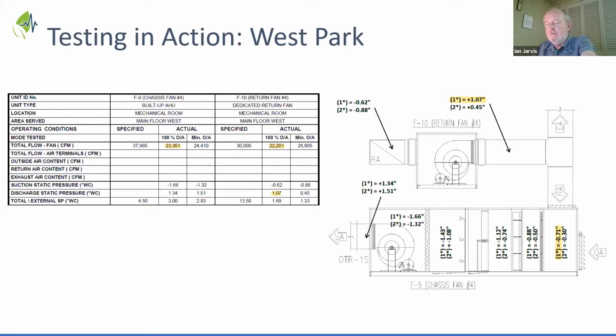But when we have the return fan at 100% outside air delivering at the top, there you'll see plus 1.07 inches. And somewhere between that and the intake plenum in the bottom right-hand corner at minus 0.71, there's a real problem here on the recirculation damper, and indeed we found that it was rusted largely shut. So the return fan's working really hard to get the recirculation running through.